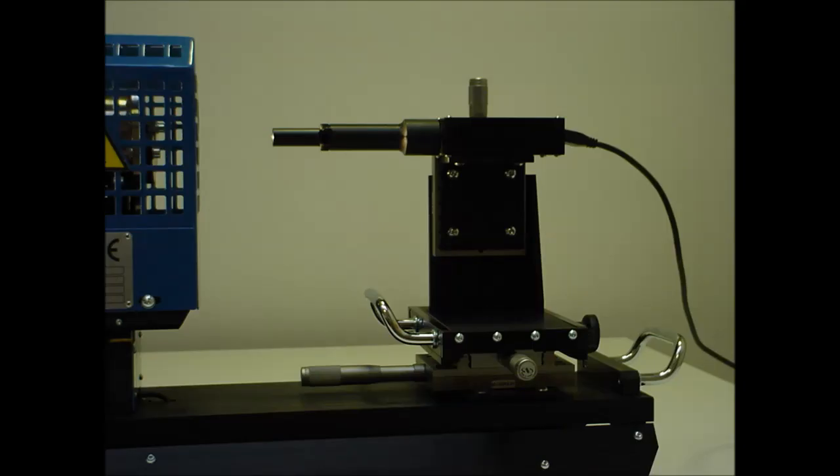The image of the sample is captured by a digital camera equipped with a microscope with a very long focal length. The image is transferred to the computer and since the picture includes the sample holding plate, the system automatically corrects for displacement of the sample holder. For this reason it is not necessary to run a calibration curve.